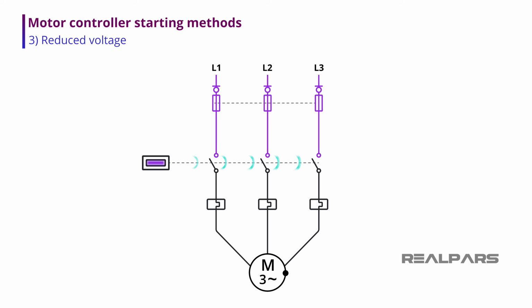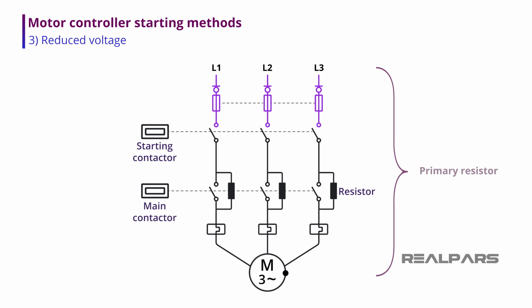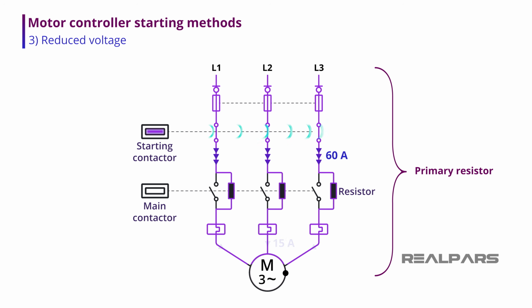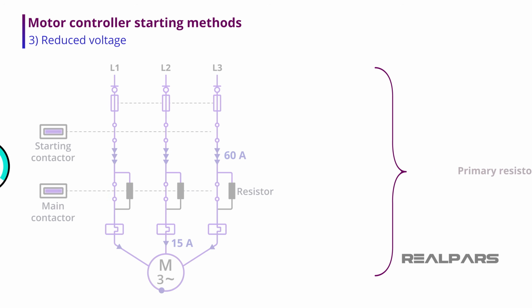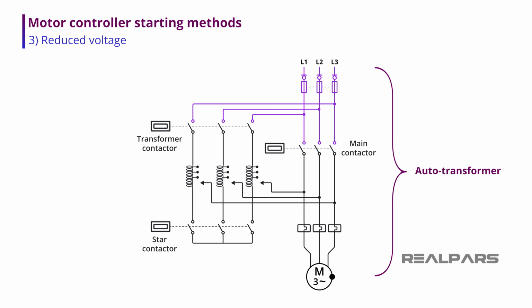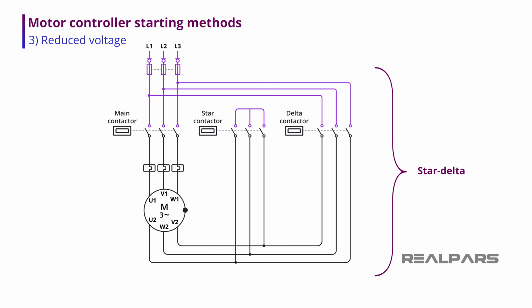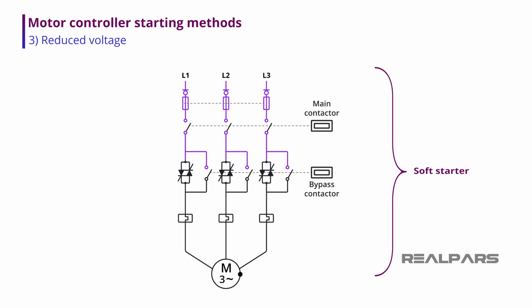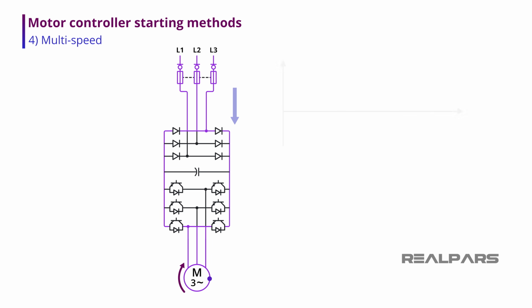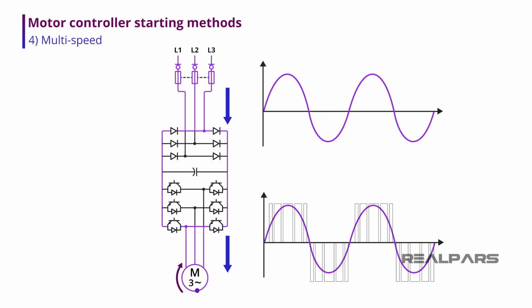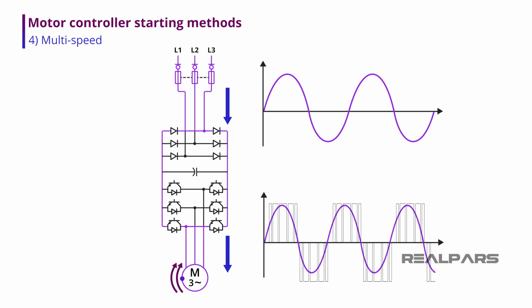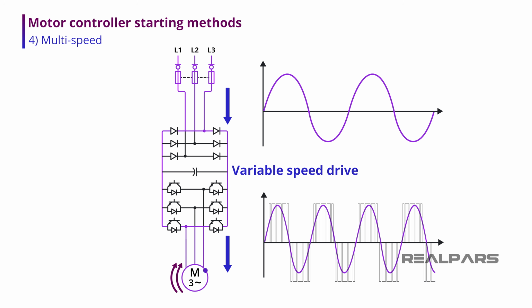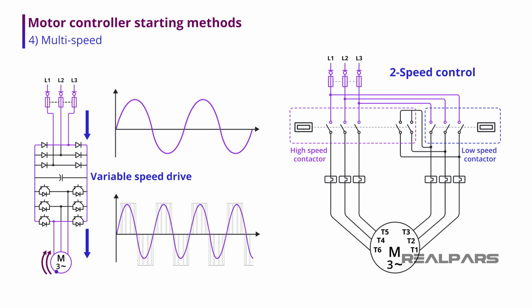Large motors can have a very high starting current that may be harmful to the motor or the motor controller itself. To limit the amount of starting current to these motors, this type of motor controller applies a reduced voltage to the motor when it first starts. There are several ways to accomplish this, such as auto transformer, star delta, and soft starter. These will be described later. The last type of motor starting method is multi-speed. Multi-speed motor controllers use solid-state or transforming means to allow motors to be controlled at different speeds. Two of these methods, variable speed drive and two-speed control, will be described later.